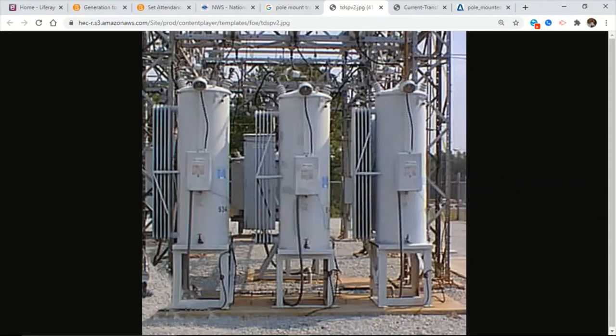Let's do a little math here. I've got three phases: this is phase A, this is phase B, this is phase C. 7,200 volts in, regulated at 7,200 volts out, optimally. If I need to stay within plus or minus 5%, what is my winding ratio?